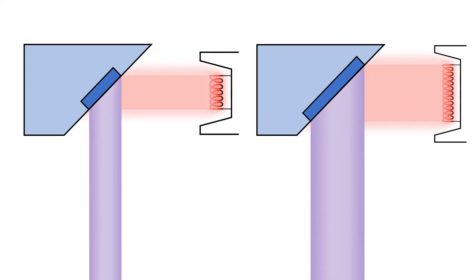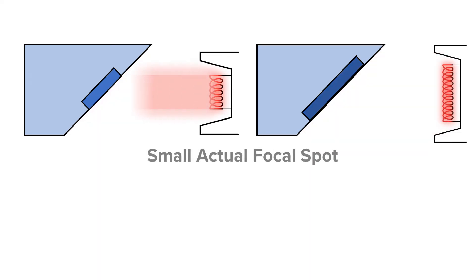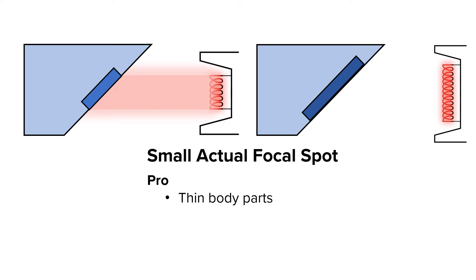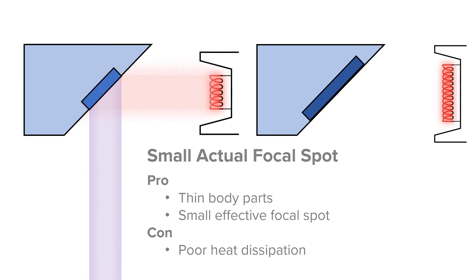There are a number of pros and cons to having a small or large actual focal spot and a number of pros and cons to having a small or large effective focal spot. The small actual focal spot has a few pros and cons. A con of the small actual focal spot is that it is poor at dissipating heat because less of the anode surface area is being used.